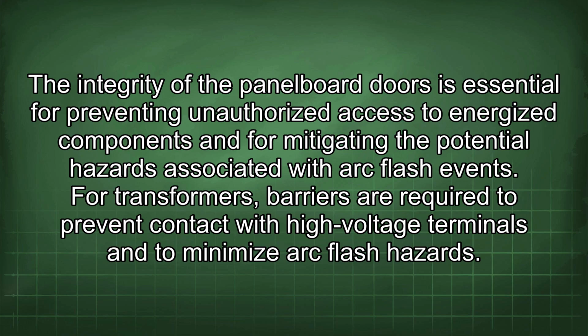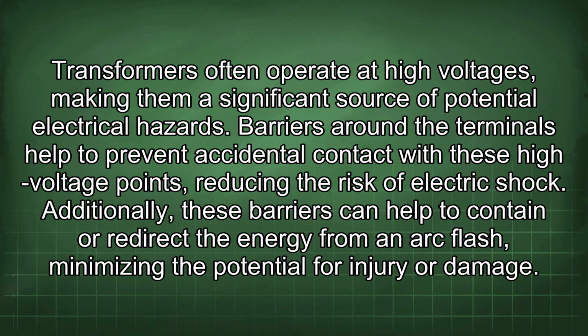For transformers, barriers are required to prevent contact with high-voltage terminals and to minimize arc flash hazards. Transformers often operate at high voltages, making them a significant source of potential electrical hazards. Barriers around the terminals help to prevent accidental contact with these high-voltage points, reducing the risk of electric shock. Additionally, these barriers can help to contain or redirect the energy from an arc flash, minimizing the potential for injury or damage.